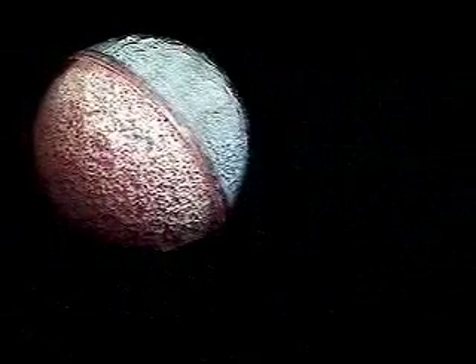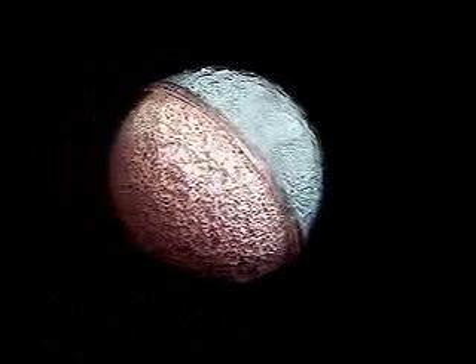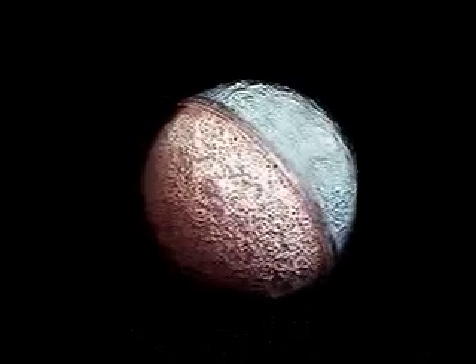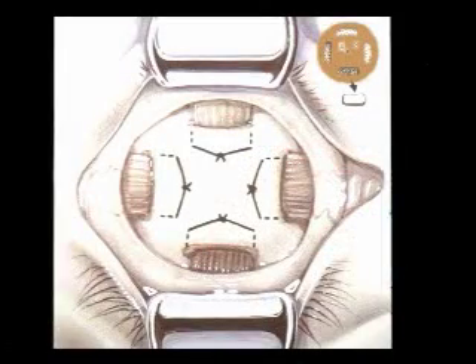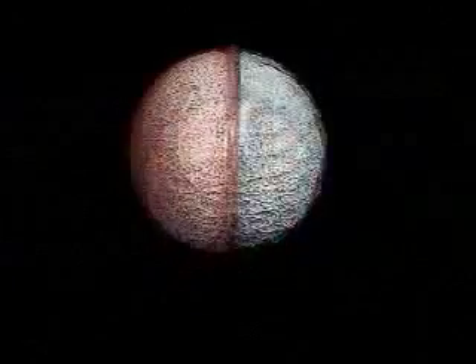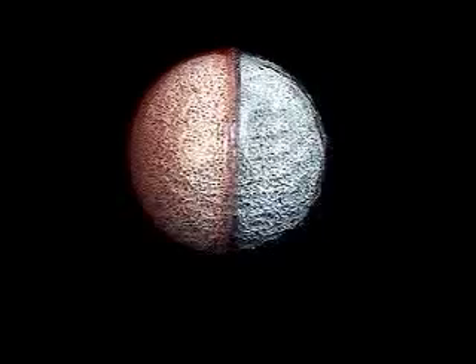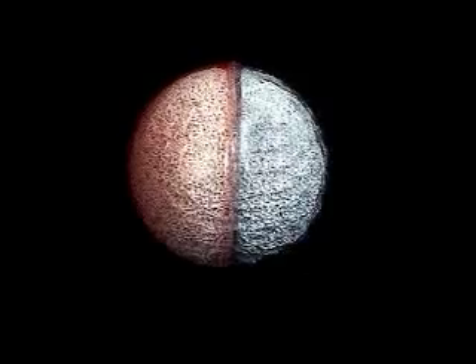With the same Bio-I hydroxyapatite implant as the core, the goal was to create an implant with a smooth, ultra-thin, absorbable coating. This coating would make the implant completely smooth so it could be easily placed deep in the orbit. The coating would allow the surgeon to attach the extraocular muscles to it, and therefore no wrapping material would be needed. The essential feature of the new implant is the polymer coating. There are actually two distinctly different polymer coatings that cover the implant, with different absorption rates specifically engineered and tested for orbital implant surgery.